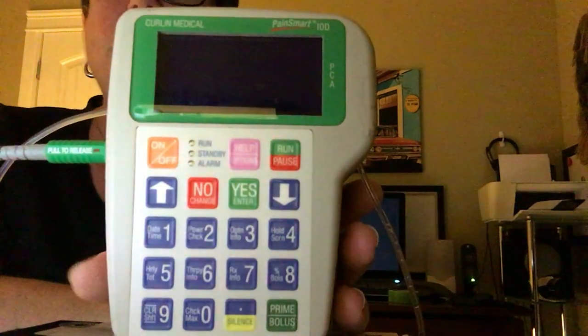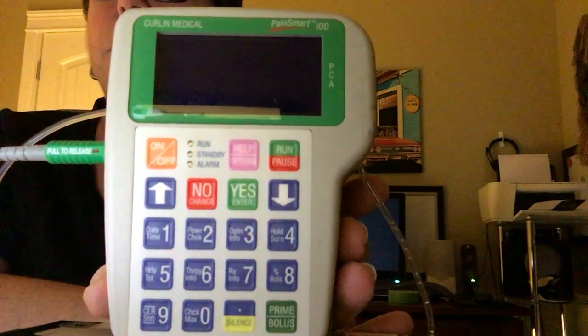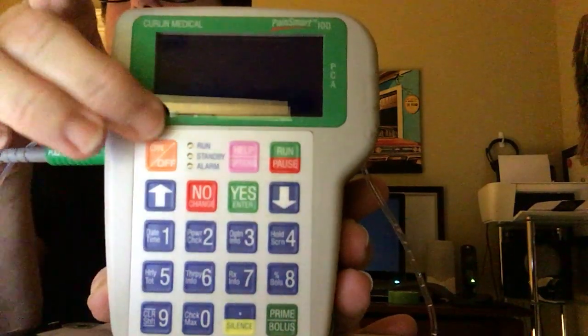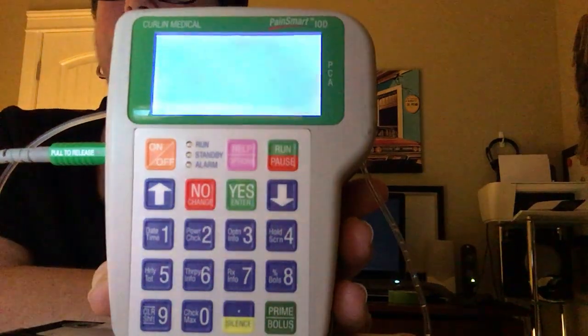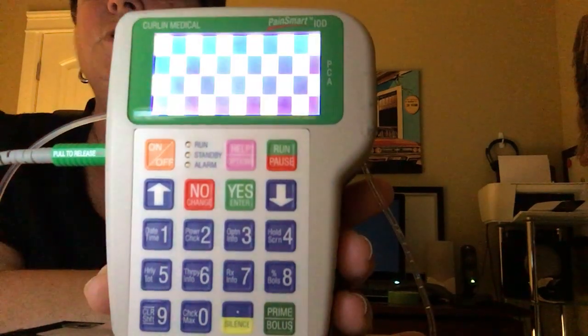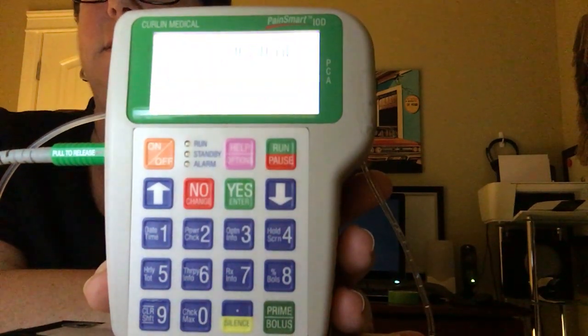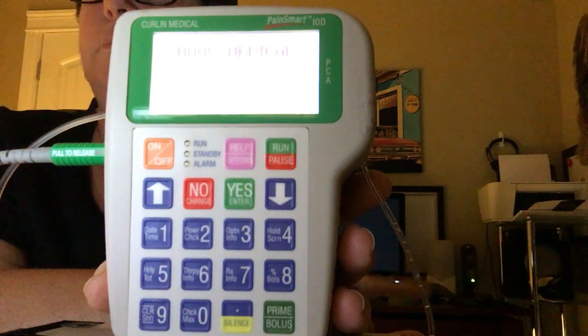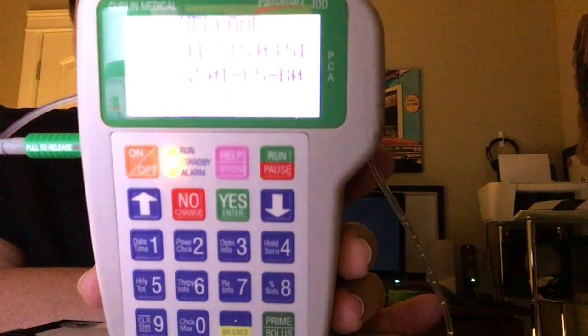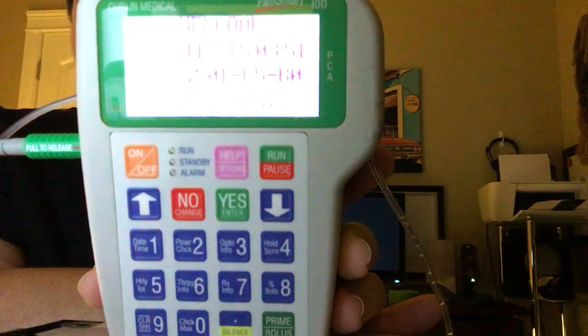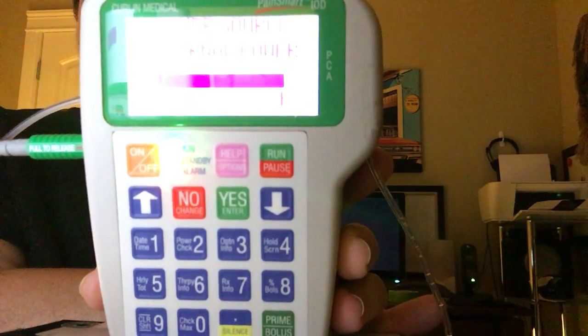In order to prime this tubing, you have to turn the pump on. So go ahead, turn it on, and you're going to get a self-test. You'll see the run button light up, the standby button, and the alarm button. And now it's also going to tell you about the external power.